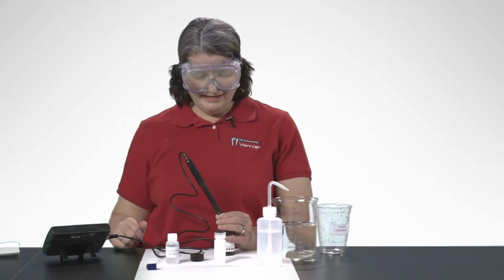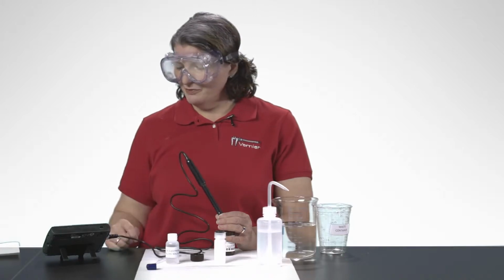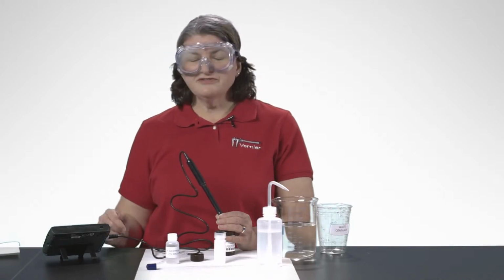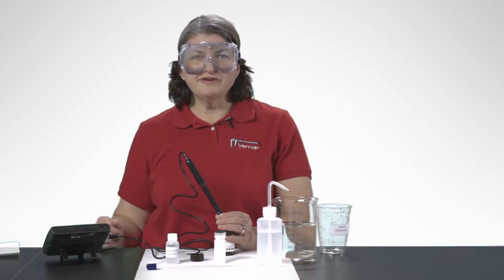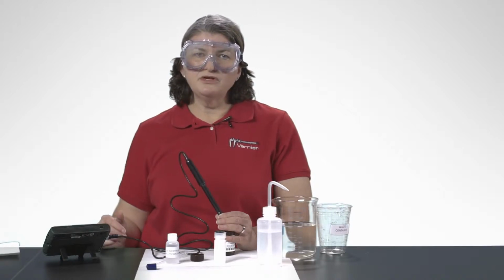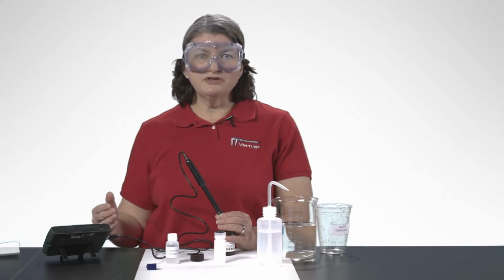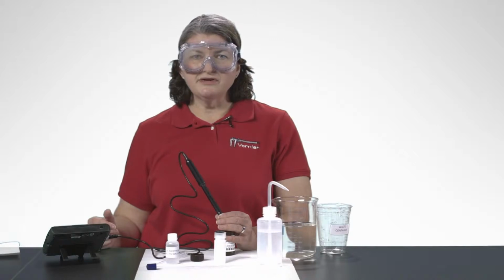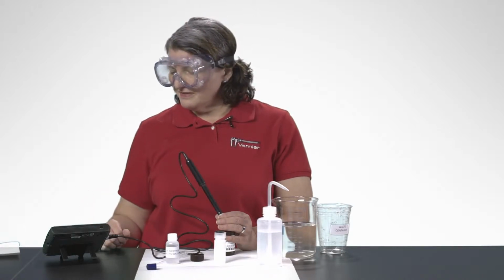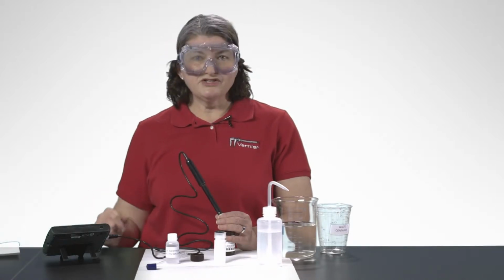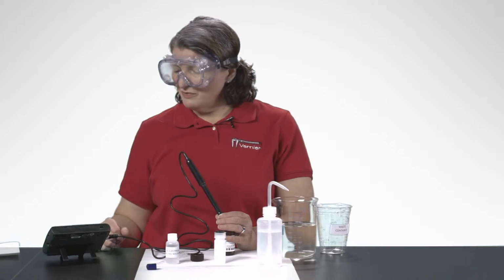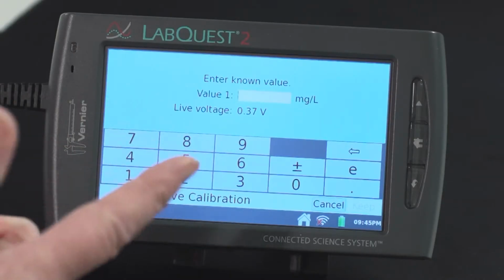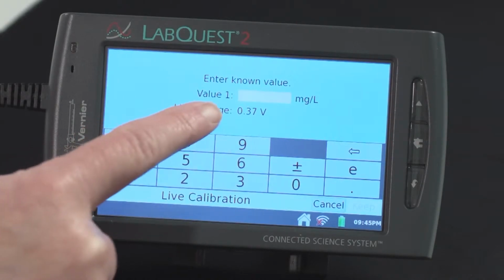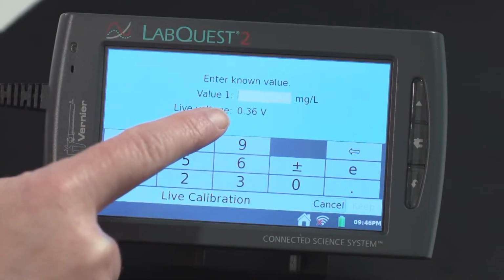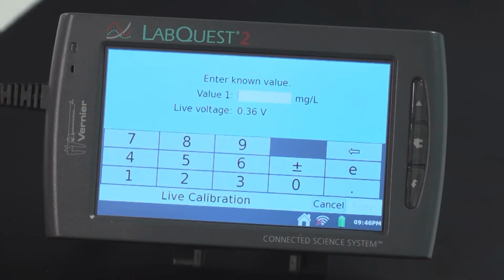If it doesn't, then you may need to replace that cap that we put on earlier. Those don't last forever. If you use this a fair amount of time, I think a lot of people replace it maybe once a semester. If you don't use it very often, maybe once a year, but they're not very expensive. So we give you 1 extra one in the box, but you may want to order some more when it's time. And this going down to something like 0.37 like we're seeing here, that's perfect. If it's not doing that, consider getting a new cap.